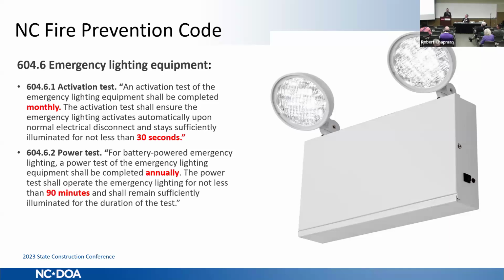All right, emergency battery units, exit signs, they have testing requirements every month. You have to do a 30-second test. You can think of the poor folks who have to go around to the ladder, push the button, go down to the next one, 25 feet, push the button. There can be tons of these things in a facility. And that's for the battery units. And even if you have a generator life safety system and all your life safety lights are on a generator, you still have the testing requirements.